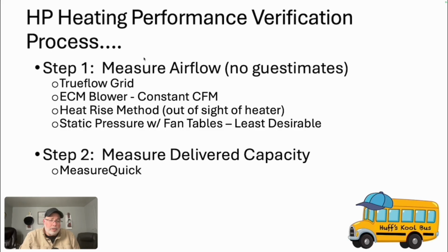Now, you may find that as you go through this process, maybe measuring airflow may uncover a problem. If it does, I would implore you to go through this process first. If you uncover an airflow problem in this process, go ahead and go through the process of measuring the delivered capacity and checking that against the OEM charts that we're going to do, and then make the correction and then go back and do it again. Why would I do that? Well, think about test in, test out.